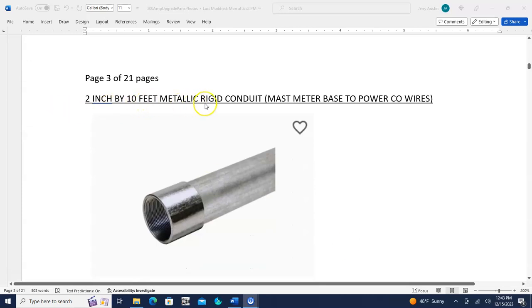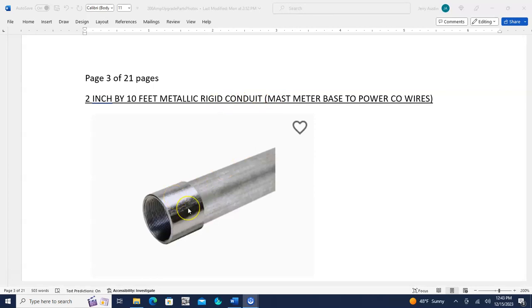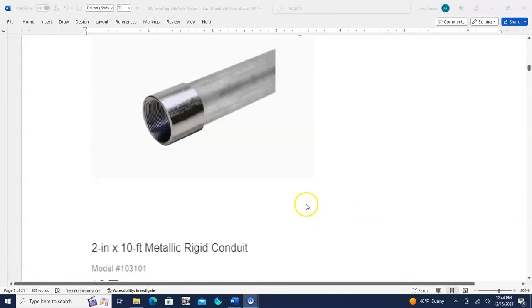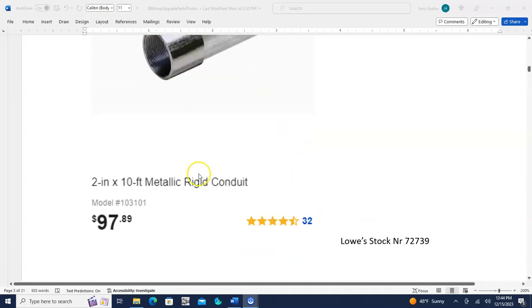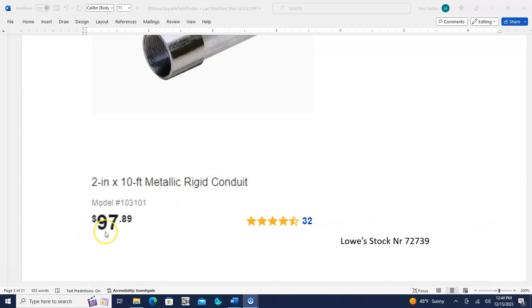This is a metallic rigid conduit mast that goes from the top of the meter base up to the power lines coming in overhead, and it screws onto a little cap that goes on top of the meter base. That's 10 foot long and anchored to the side of the house. It's a 2-inch by 10 foot metallic rigid conduit. There's a Lowe's stock number, and that's what it costs.